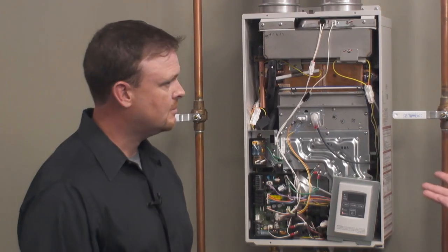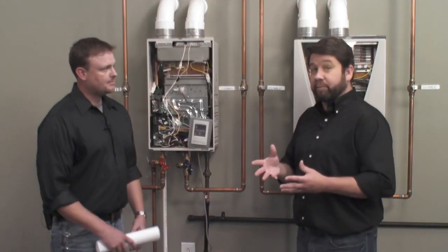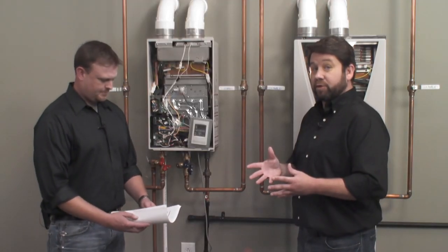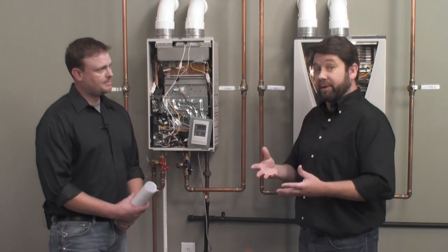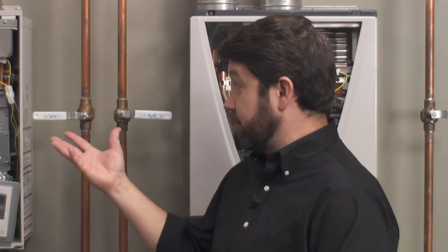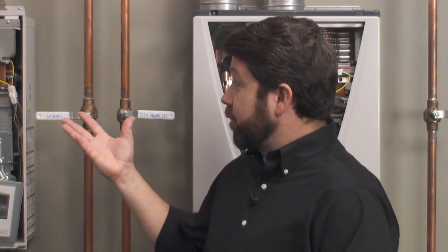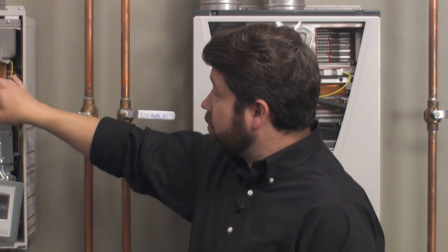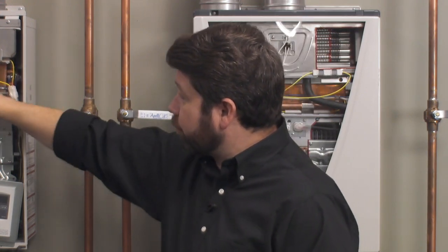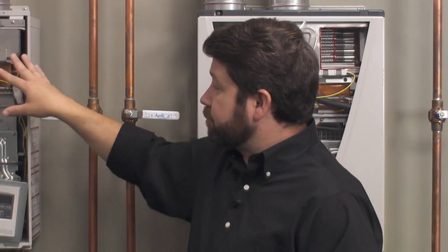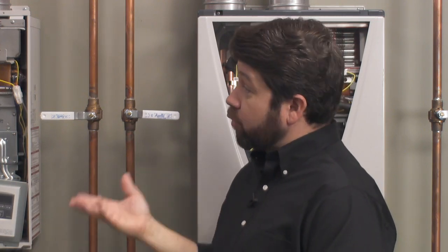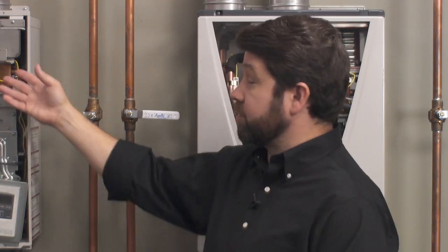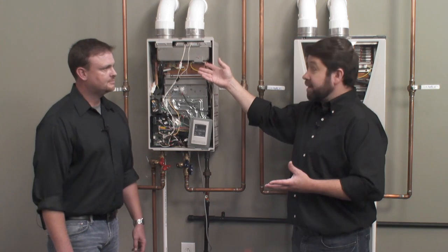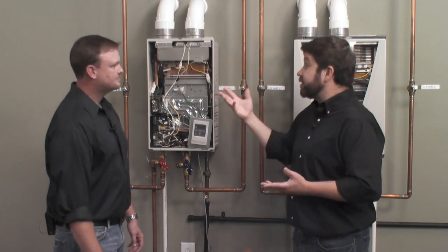With freeze protection, you always want to take every precaution possible to prevent freezing, so you don't want to install the water heater in an area where freezing may be prevalent. We do have freeze protection though, in these little yellow wires that go to all these little ceramic block heaters. They're positioned strategically throughout the heater to provide protection. At 36 degrees, we'll energize that circuit. Those will heat up and prevent freezing from happening.